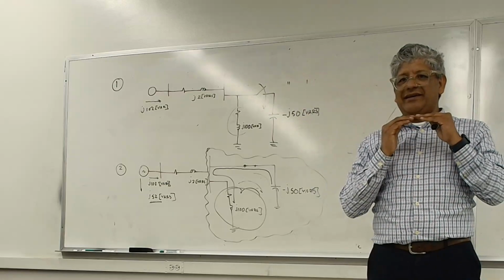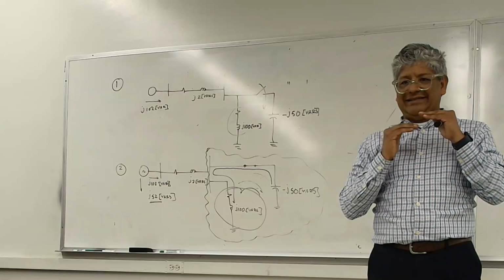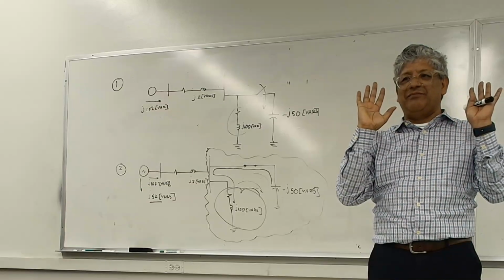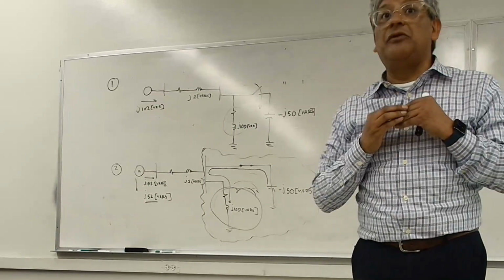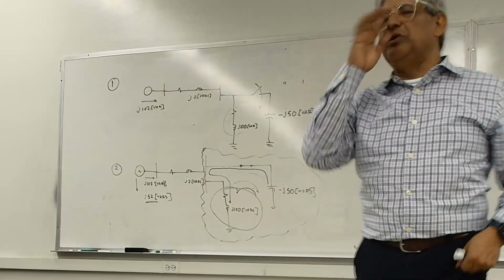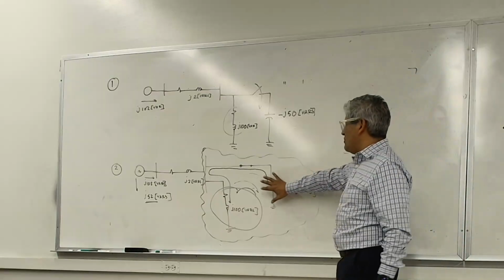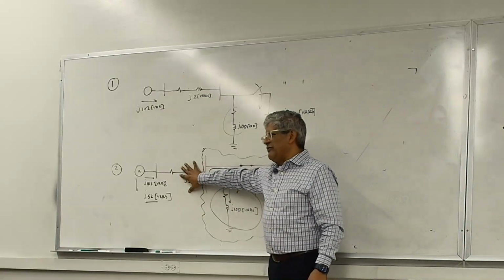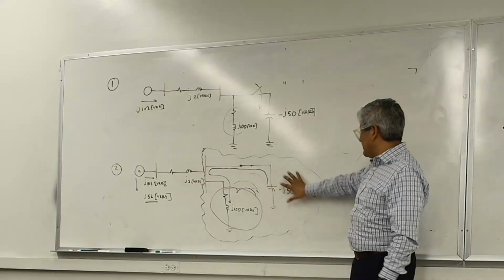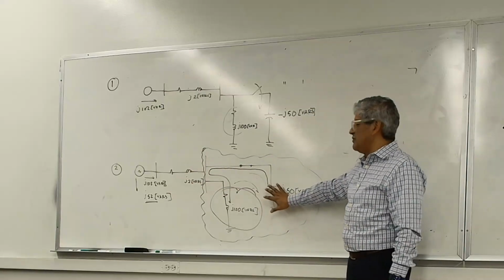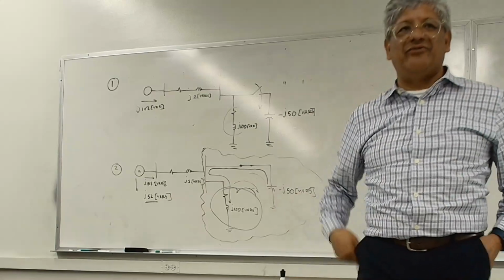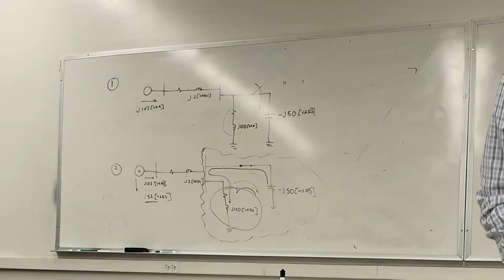Again, it's a question of economics. If I can get away with making it 0.83 and the utility will forget about me, that's what I'm gonna do. Businesses will do the bare minimum, right? And we'll get to that. We'll get to how we size it. First we gotta measure the power factor that the utility sees, then we gotta improve it by using capacitor banks. How do we determine that? How do we quantify the amount of VARs? That's what we're gonna do next.